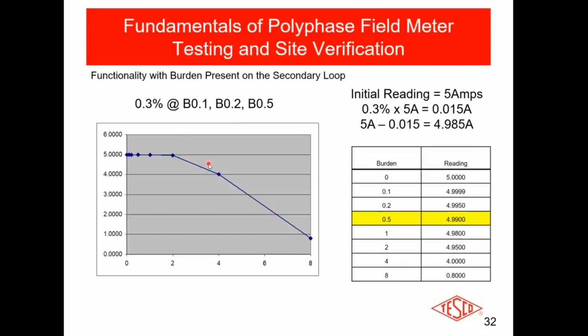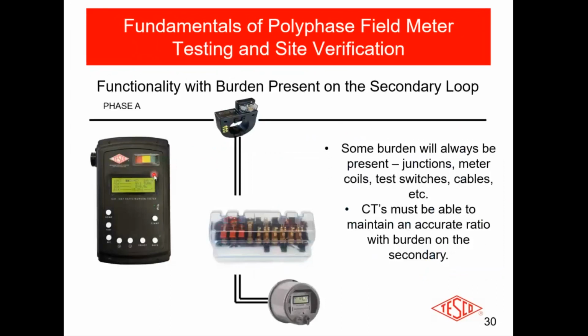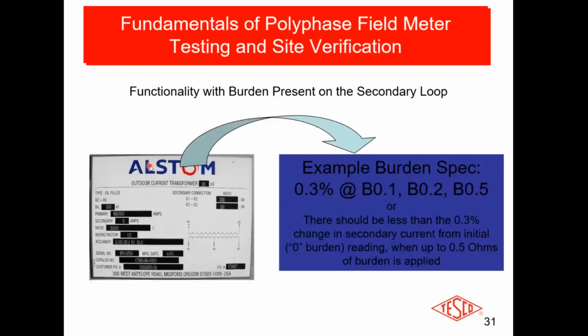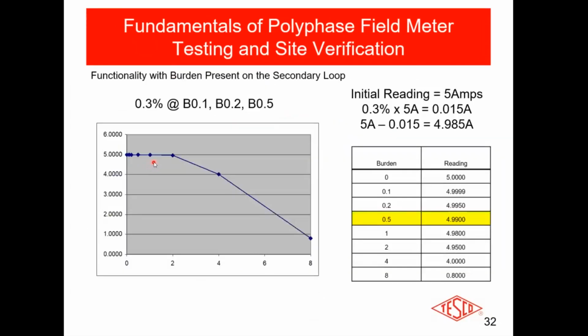So one thing that you check when you go out to a site, you take ours or anybody else's burden tester and you do a burden check on your CTs, okay? It's a nice, important test. Typically we've got red, yellow, green. It's pretty self-explanatory. If it's in the red, you've got a problem, all right? And if you've got a problem, you do want to address it because those CTs may be giving you very inaccurate readings now, okay? As you can tell, it quickly drops off, all right?